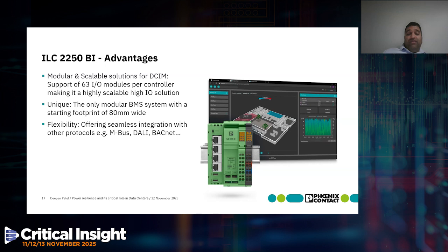The controller also offers seamless integration, so you can integrate your lighting and typical building control protocols like BACnet, both IP or MSTP. MBus is a typical metering protocol for all your MBus meters. You can bring all these protocols into the controller natively, which is very powerful because it minimizes the need for gateways and improves savings in engineering time, integration with the system, and system availability.